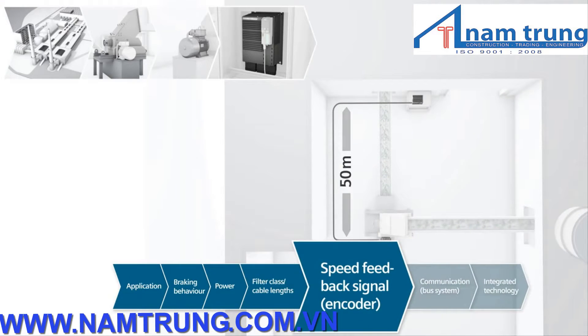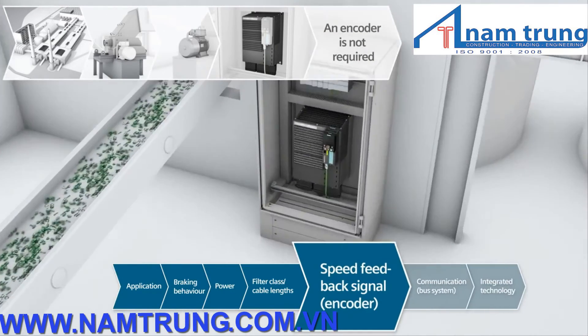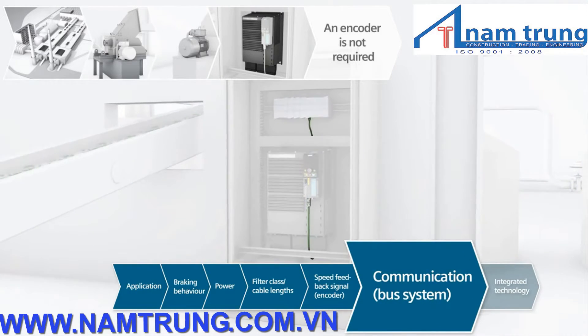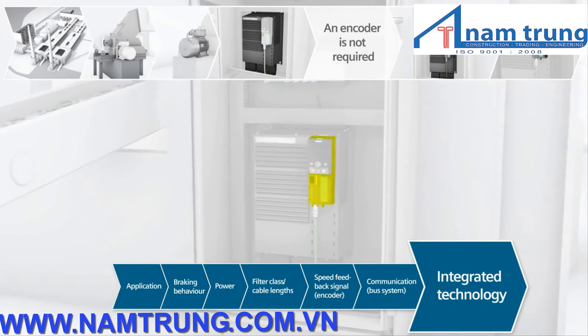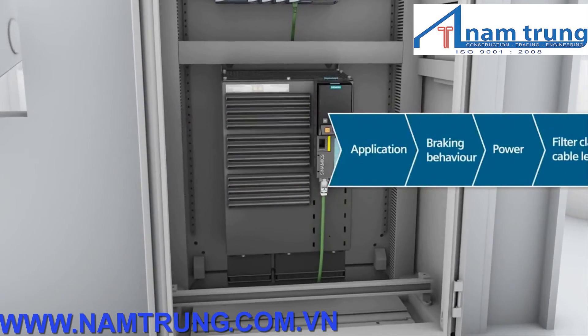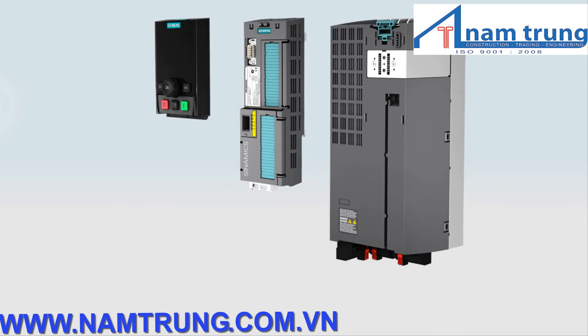Will an encoder be used to feedback the speed signal? No, the crusher does not require a speed feedback signal. What type of communication is used? The crusher is controlled via a PROFINET communication interface. Is special safety technology required? The crusher should be safely brought to a standstill. The use of integrated safety technology optimally fulfills this requirement — without requiring any additional components. And that was it. SINAMICS G120 has now been configured and can be used in the application.